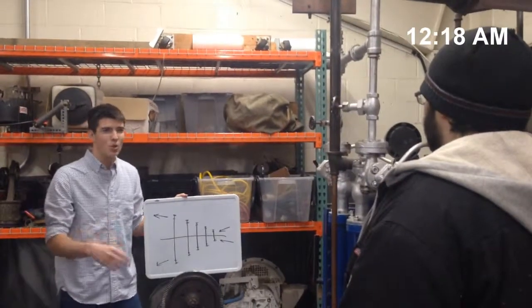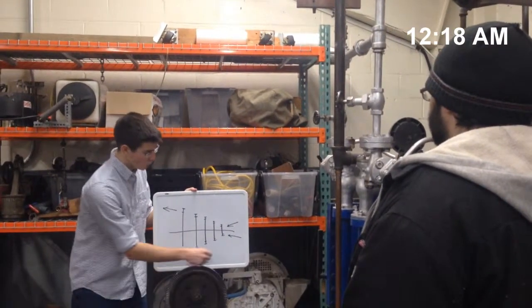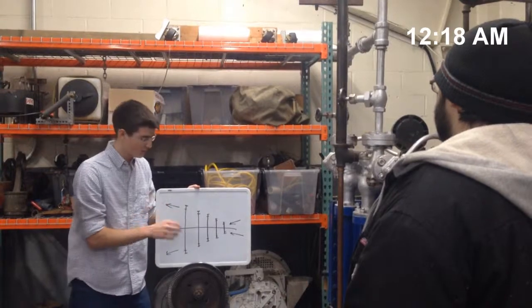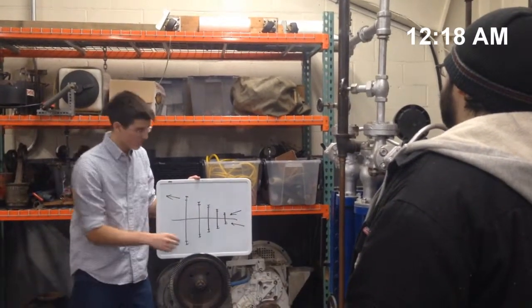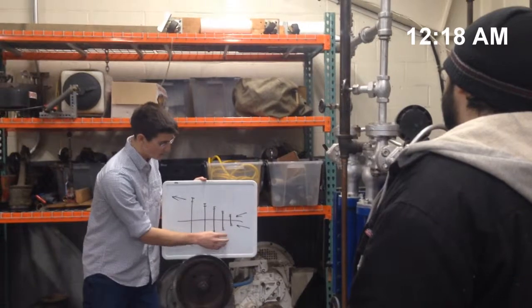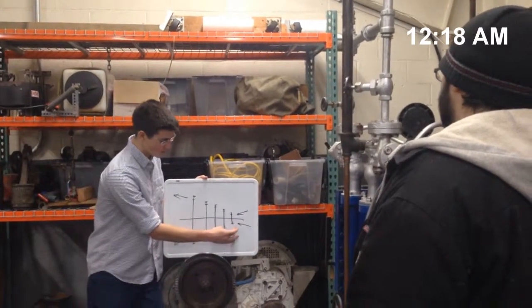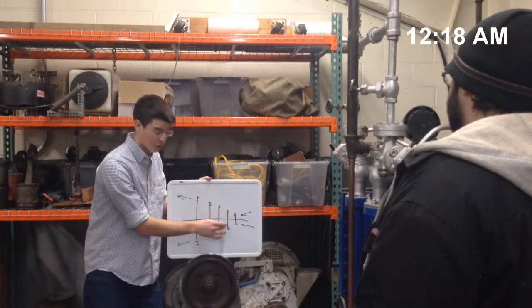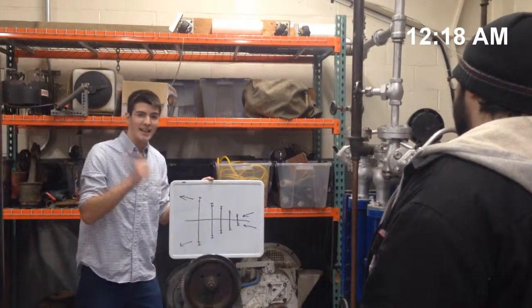One thing to know: as we pass through the turbine, through each stage there's a pressure drop, and therefore a decrease of force acting on each blade. To counteract this, we must mount the blades further from the shaft to maintain the level of torque needed. Therefore, as we go through the turbine, blades are mounted further and further from the shaft.